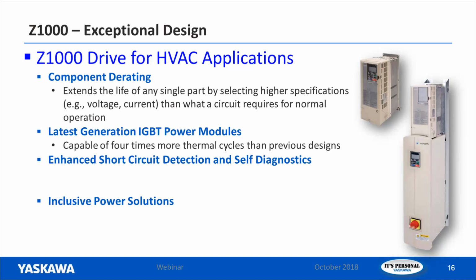We use the latest IGBT power modules. We have enhanced short circuit detection and self-diagnostics. The Z1000 drive is our first series that came out in the HVAC that doesn't need a DC bus fuse. With our enhanced short circuit protection, we don't need it anymore.